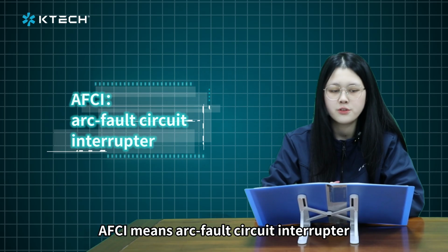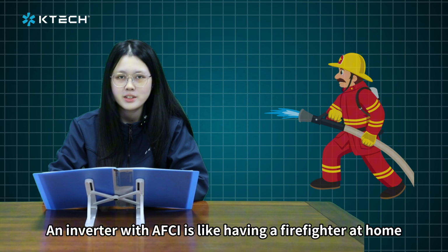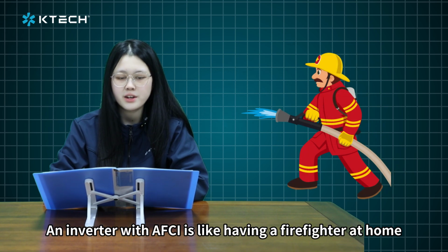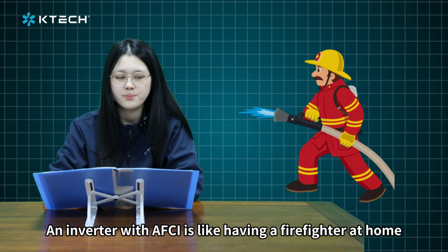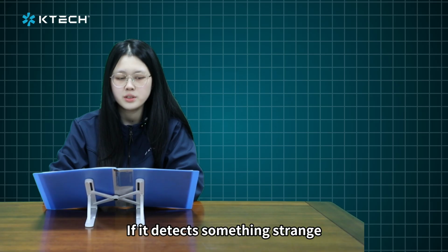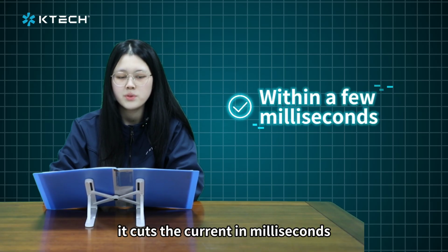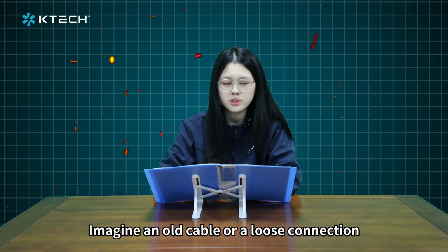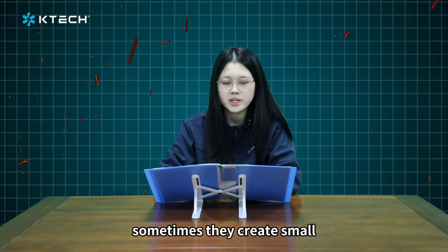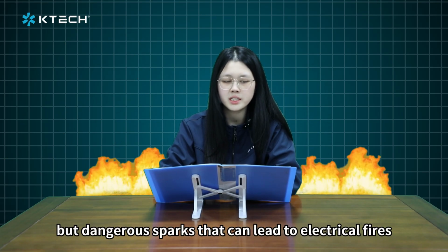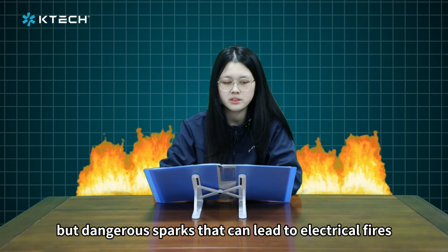The second one is AFCI, the safety guardian. AFCI means arc fault circuit interrupter. An inverter with AFCI is like having a firefighter at home. If it detects something strange, it cuts down the current in milliseconds. Imagine an old cable or a loose connection. Sometimes they create small but dangerous sparks that can lead to electrical fires.